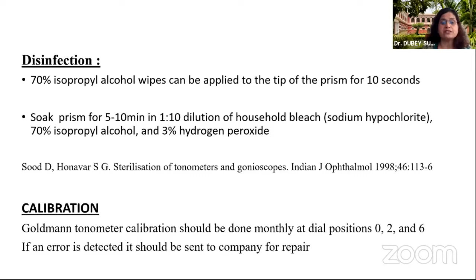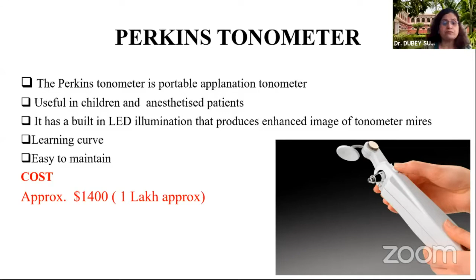Therefore, it is useful in children and anesthetized patients, and it has a built-in LED illumination that produces an enhanced image of the tonometer mires. But I would say that it has a learning curve because whenever you're measuring the IOP, your hand may not be stable, and the illumination area is also small as compared to the slit lamp mounted applanation tonometer. And the cost is approximately 1 lakh.